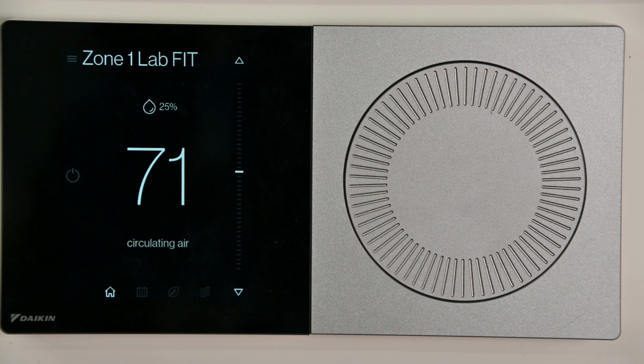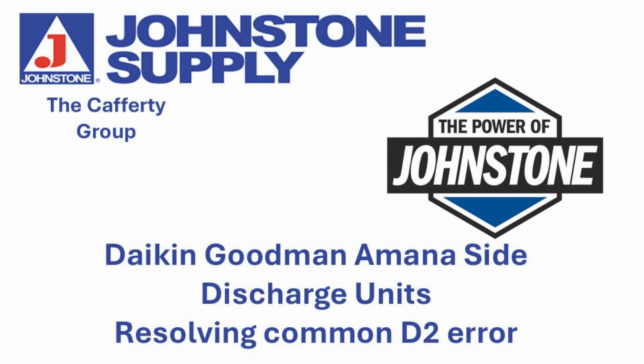In this case, I'm just going to go ahead and exit since I did not run the system test. The D2 should go away. At this point, you may re-enter and change the trim rates to a slightly more desired setting to see if the D2 comes back. If those changes don't resolve the D2 error and allow the system test to operate, we may have a communication error or a data error. We can do a separate video on that, and of course always contact us for discussion.